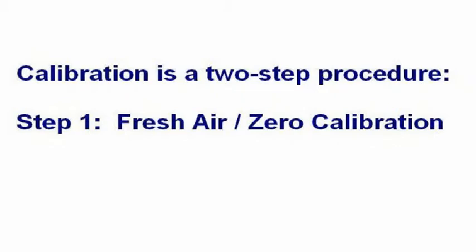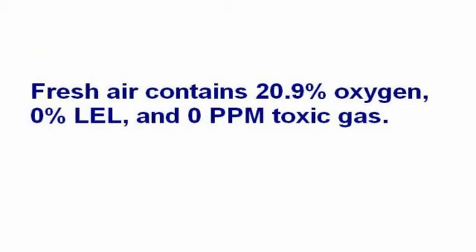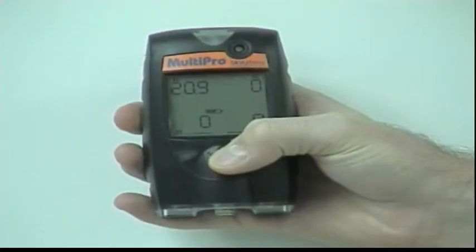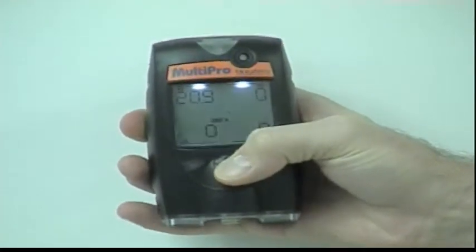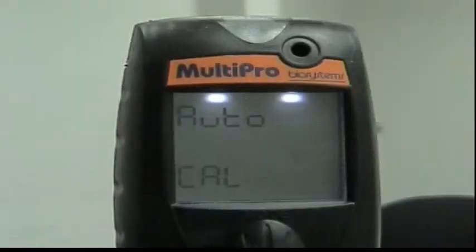Calibrating the MultiPro is a 2-step procedure. Step 1 is the fresh air or 0 calibration adjustment. Take the instrument into an area where the air is known to be fresh. Press the mode button 3 times within 2 seconds to initiate the fresh air 0 calibration sequence. The instrument will show auto cal briefly before showing 0 cal and beginning a 5-second countdown.